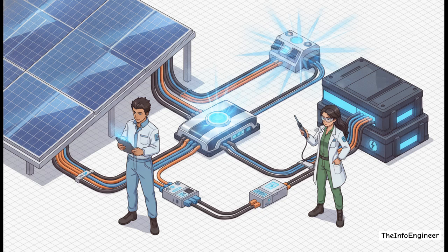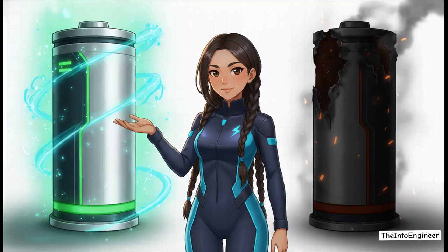And crucially, you have to precisely calculate wire sizes against the total load distance. If you fail to account for long cable runs, you are going to suffer hazardous voltage drops that will completely cripple your system's efficiency. And speaking of efficiency, here's a massive factor for solar economics.